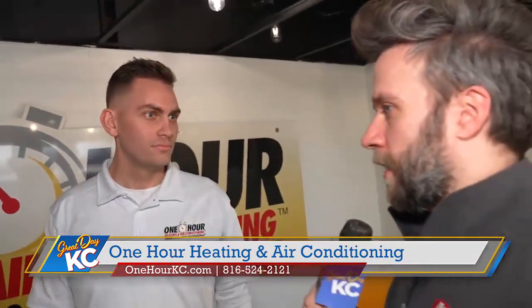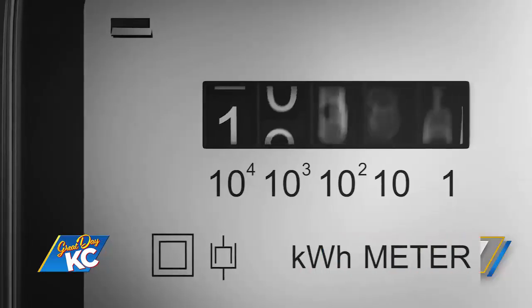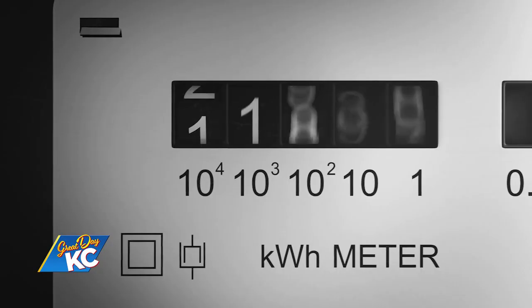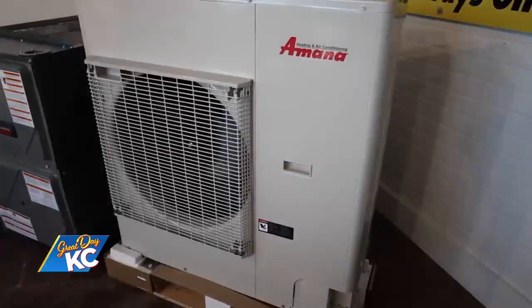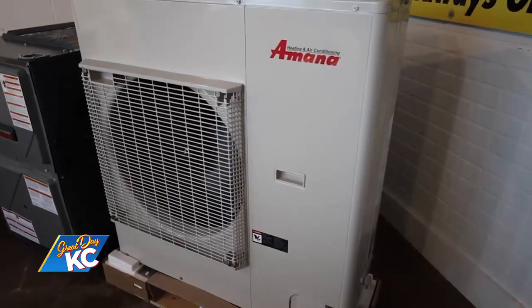That sounds like it could lead to more efficiency. So talk to me about the energy efficiency. Is the fact that it's running longer using more energy? So it's an inverter unit. Most systems run off of alternating current, AC. These are inverted to DC current, so it uses significantly less power when it is running. It actually runs at 35% of its capacity, 85% of the time. It's using so little power that you're saving quite a bit in the long run.